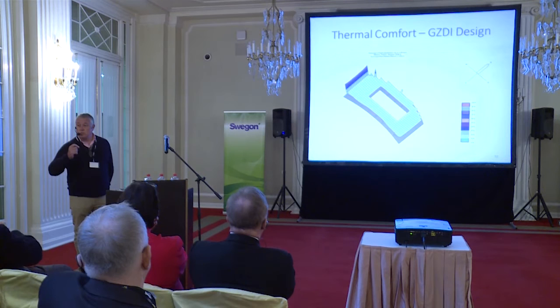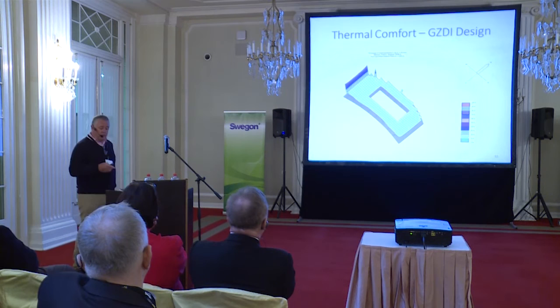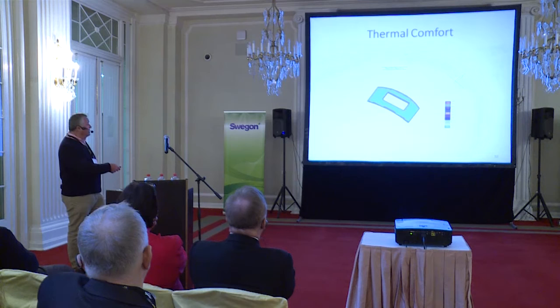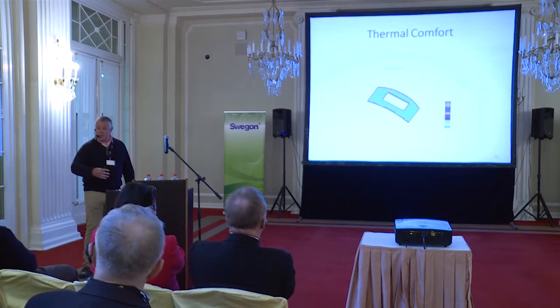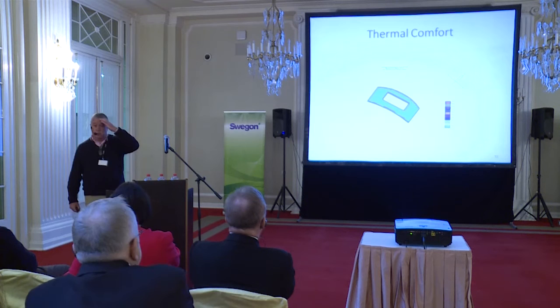So how do we do it? We start looking around for different choices, and we get into the green, we get below 10%. With the mixture of the radiant ceiling, the double skin facade, and the underfloor distribution, when it all comes together, we get less than 10%, which is the minimum level we have for compliance for thermal comfort.